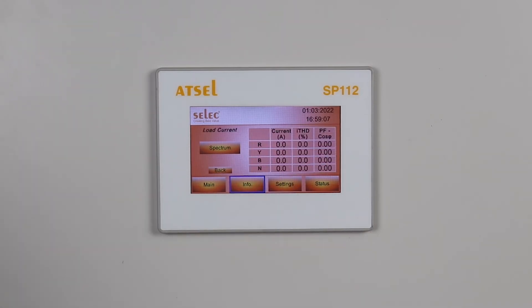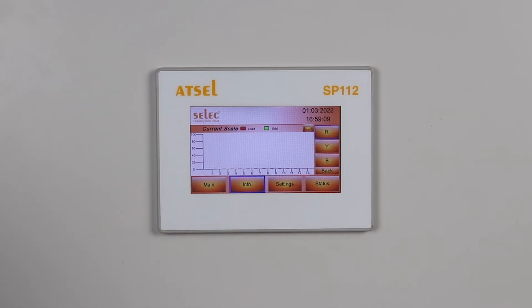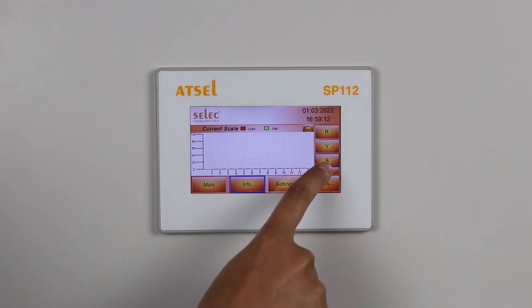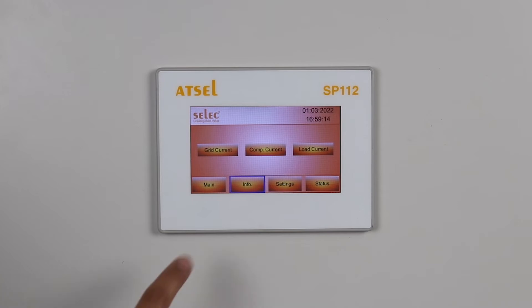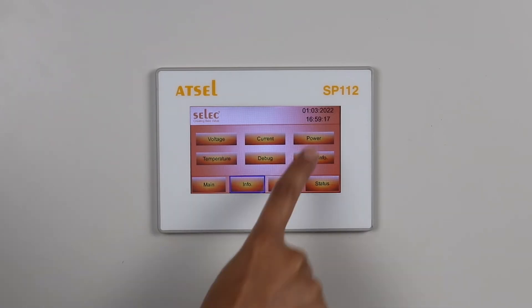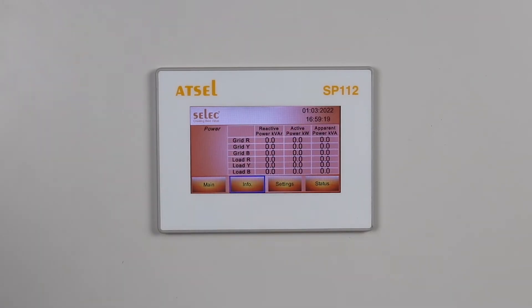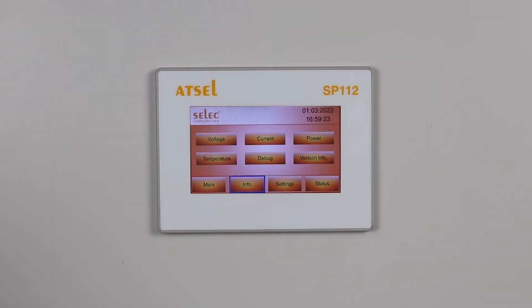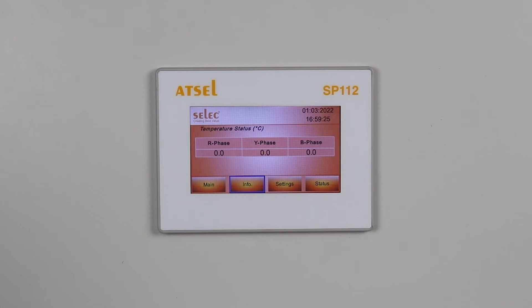If you go to load side current, you will get all 4 phases — RYB and neutral current — their total harmonic distortion and power factor. You will also be able to see the spectrum. Power shows individual phase power on the grid side as well as the load side, and all 3 types of power: reactive power, active power, and apparent power. In temperature, individual IGBT temperatures are displayed.